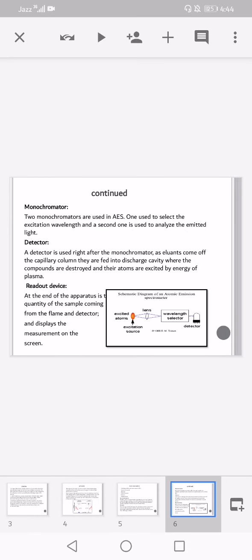Monochromator: two monochromators are used in atomic emission spectroscopy. One is used to select the excitation wavelength, and a second one is used to analyze the emitted light. A detector is used right after the monochromator. As elements come off the capillary column, they are fed into the discharge cavity where compounds are destroyed and atoms are excited by the energy of the plasma.